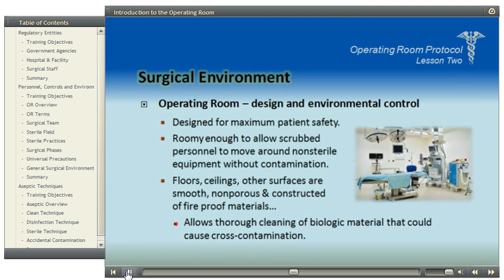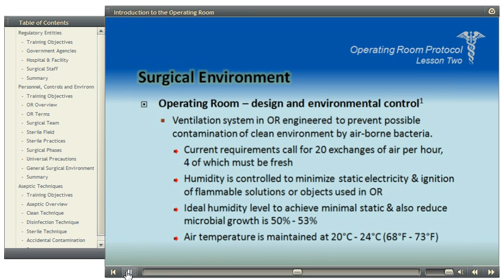Operating room, design and environmental control. Ventilation system in OR engineered to prevent possible contamination of clean environment by airborne bacteria. Current requirements call for 20 exchanges of air per hour, 4 of which must be fresh. Humidity is controlled to minimize static electricity and ignition of flammable solutions or objects used in OR. Ideal humidity level to achieve minimal static and also reduce microbial growth is 50% to 53%. Air temperature is maintained at 20 degrees Celsius to 24 degrees Celsius, 68 degrees Fahrenheit to 73 degrees Fahrenheit.